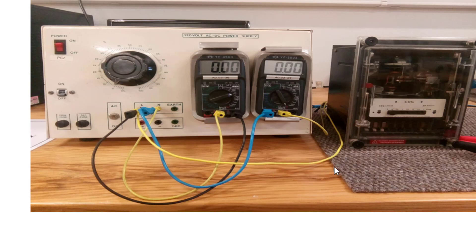So after you have all of that set up, you turn the power on and you start your stopwatch. Your stopwatch is going to start running the seconds. The disk is going to start turning, and when the disk trips, you stop your stopwatch. And that's the time you're going to record. That's the time it took the disk from when it started turning to when it tripped and your flag was tripped. You're going to record your time and the amount of current set up. Those are the values you're going to use for your plot. It's basically the time using your stopwatch and the amount of current using your plug settings.